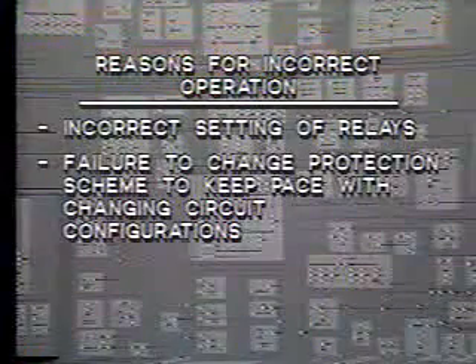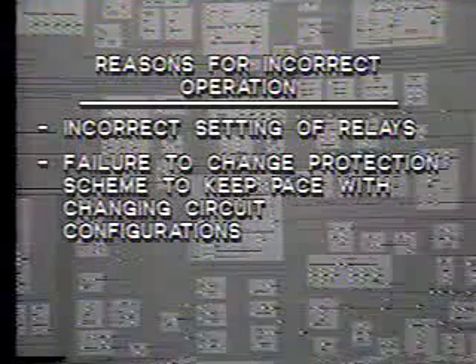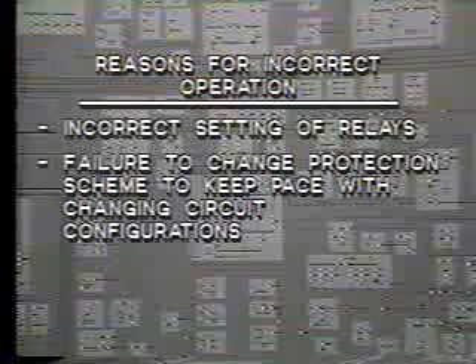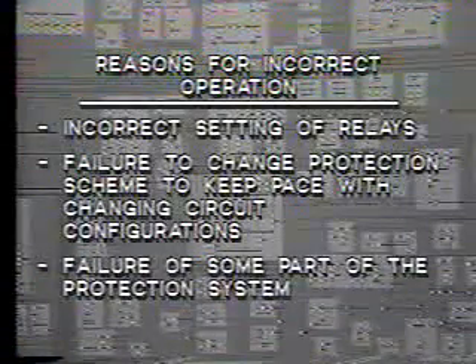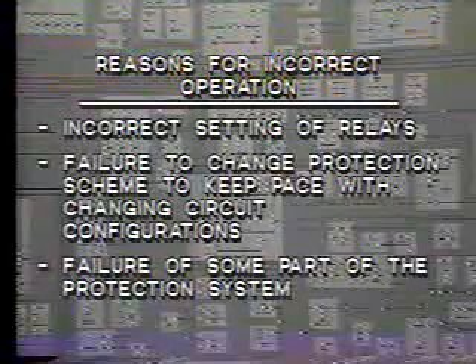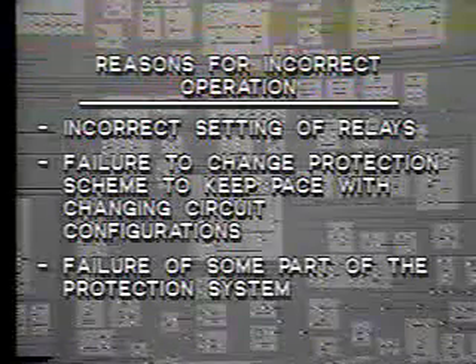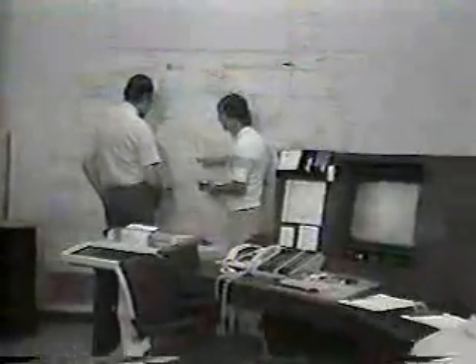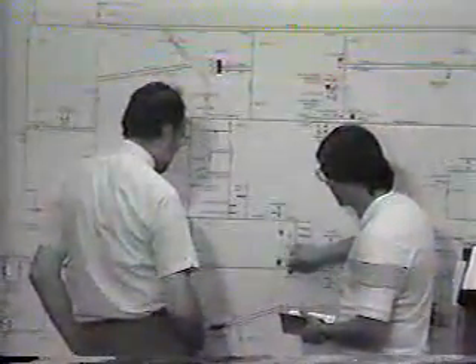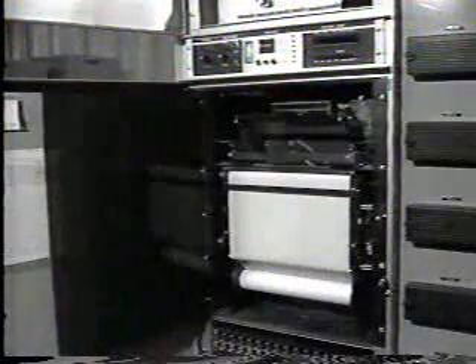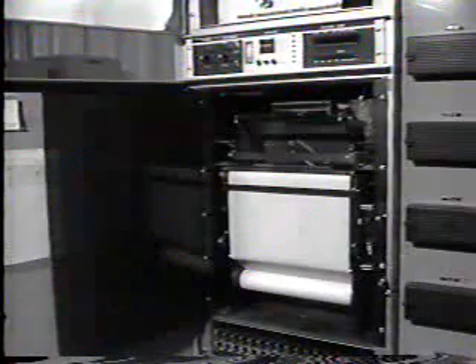The reason for incorrect operation of the protection system could be, one, incorrect setting of relays, two, failure to change protection scheme to keep pace with changing circuit configurations, that is, inadequate protection, or three, failure of some part of the protection system, such as the relays themselves, breakers, CTs or VTs, the station battery, the circuit wiring, and so on. With all of the variables involved, it's often quite difficult to carry out this post-mortem and deduce what actually happened. Fortunately for us, nowadays most power systems have installed data recording equipment, oscillographs, and fault indicators that will indicate conditions before and after the fault. These provide valuable assistance in evaluating the actual performance of the protection system.